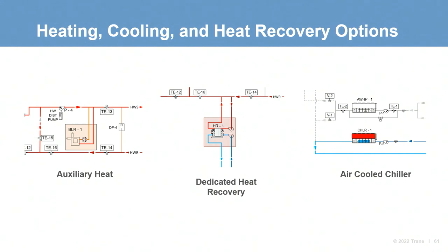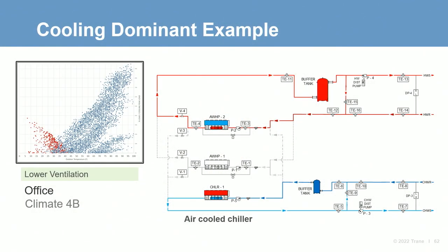Depending on the specific building requirements, there are options to increase efficiency, increase accuracy of control, and/or improve redundancy. Let's take a look at what some of those options could be. This example shows how configurable the system can be. Recall our earlier example of an office building with a low ventilation rate that has a much larger cooling load than heating load. Instead of sizing the heat pumps to satisfy the cooling load, why not incorporate some chillers into the cooling production side? Air-cooled chillers utilizing scroll, screw, or centrifugal compressor technologies can be easily incorporated to the system. Chillers would also be less upfront cost and more efficient to operate, so overall savings can be increased.